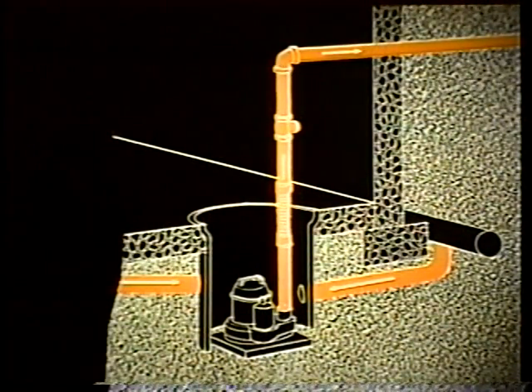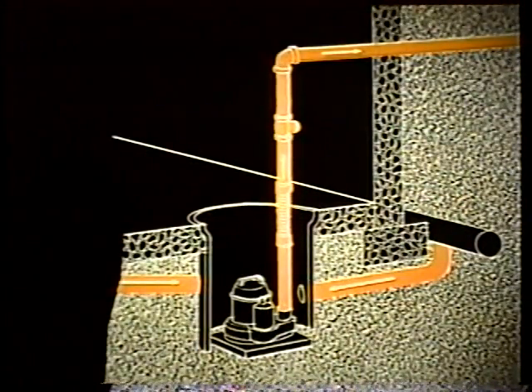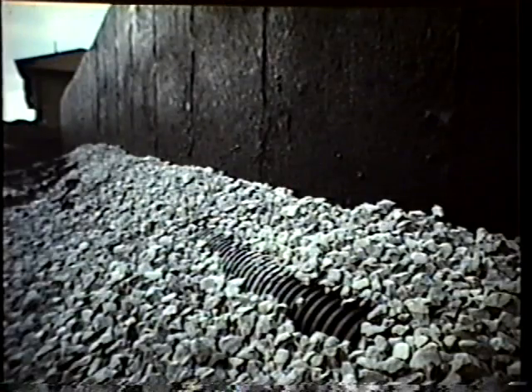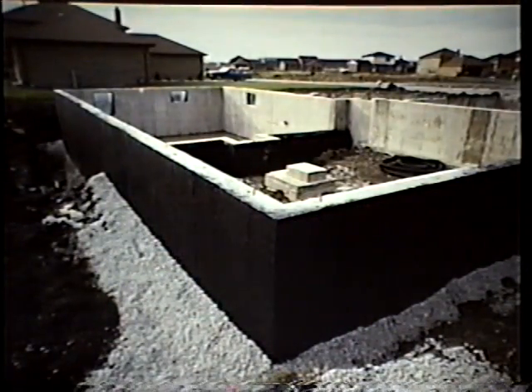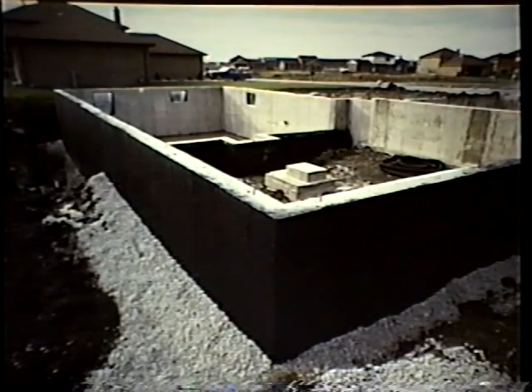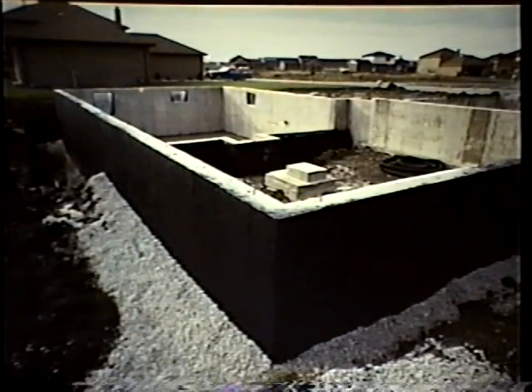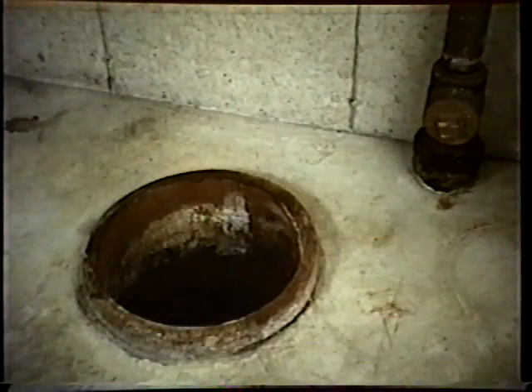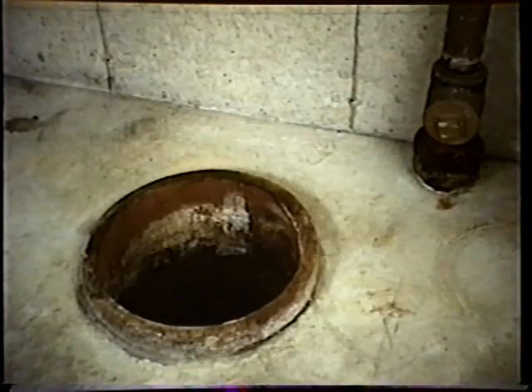A typical new intake, collection and discharge system consists of a drainage system and a sump. In a new home, it's wise to plan for the perimeter tile, since this will help avoid flooding inside the basement. In an existing home, decide whether you want to drain the basement only, or whether you also want to install tile underground around the perimeter of the basement to remove water that's close to the house. Drainage is usually collected in a storage basin or pit inside the house, but occasionally perimeter water can be drained to a storage basin outside the house and pumped away from there. Most commonly, sumps are put inside a dwelling, in a basement. The sump should be located about six inches from a wall. If there is no floor drain draining into the sump pit, the sump should be located at a low point of the floor, so that liquids will drain into the sump.